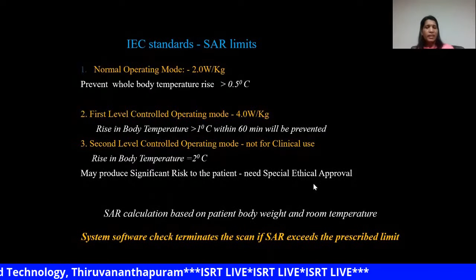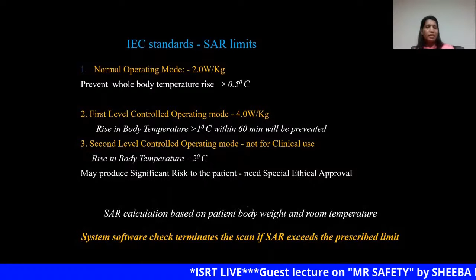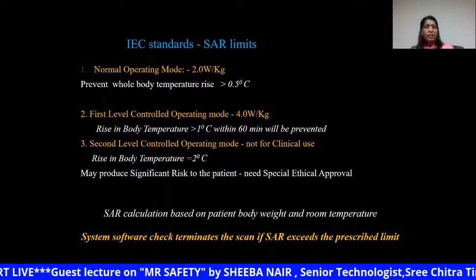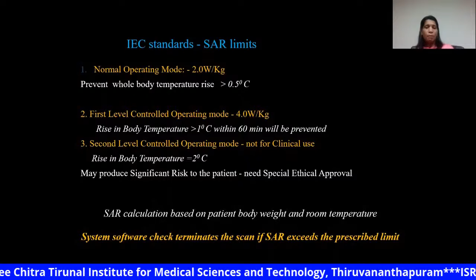In the second level mode, there can be significant risk to the patient, so this needs special approval from the ethics committee. The SAR calculation is based on the body weight and the room temperature. So it is very, very important that while starting the scan, we enter the patient's body weight correctly, and also that we are alert to the system pop-ups. When the SAR limit is exceeded, the system pop-ups will come.